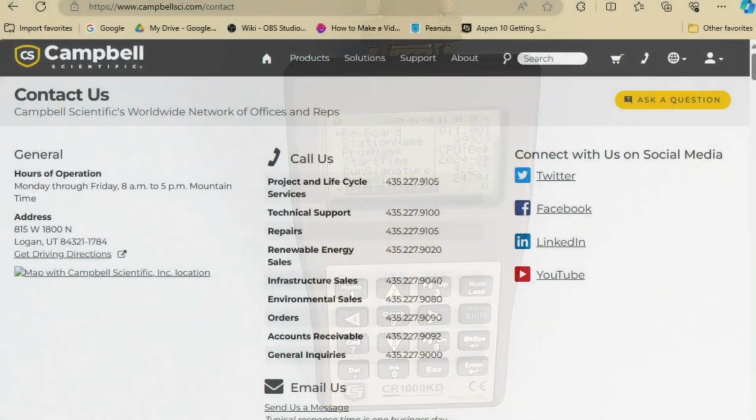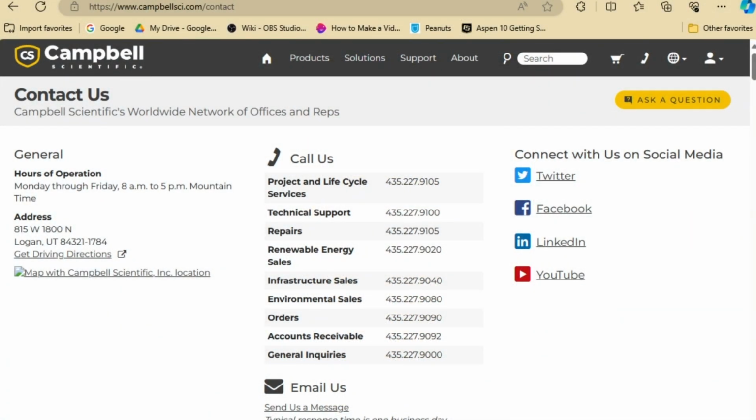The field called Watchdog Errors is a counter that indicates the number of times that the data logger's processor has stopped and had to be restarted. Occasional watchdog errors are normal, but if there are a high number of watchdog errors, your system may have a failing component, unstable power supply, or program error that is keeping the data logger from operating properly. In that case, contact Campbell Scientific Support to help resolve the issue.